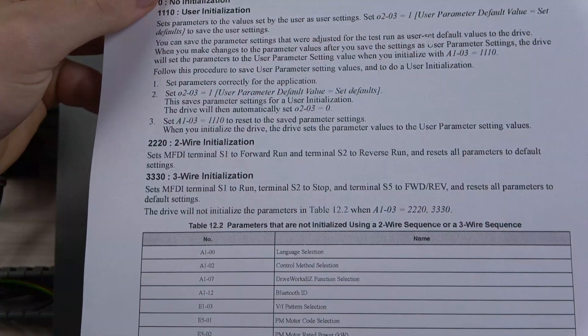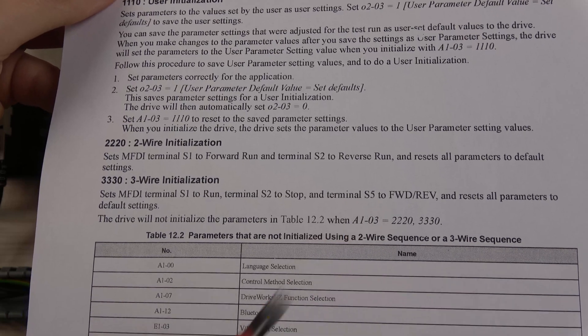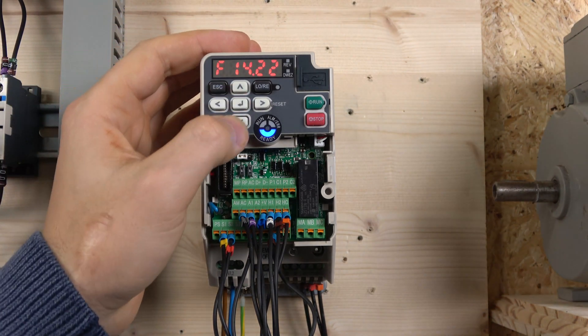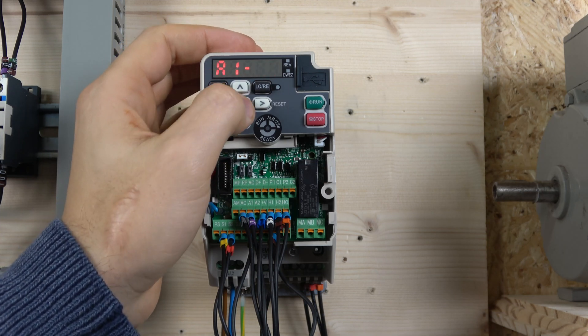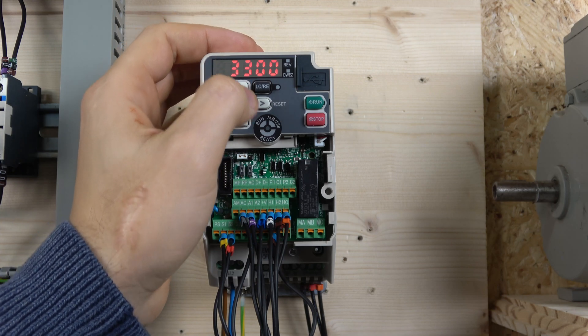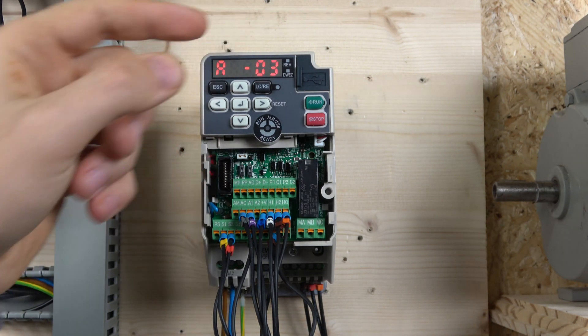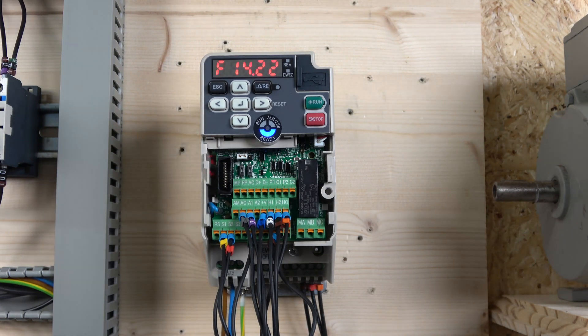In three-wire control mode, S1 becomes the run terminal, S2 becomes the stop terminal, and S5 is used for forward and reverse selection — the remaining S terminals can still be programmed freely. To set this up, go into parameter A1-03, enter the value 3330, and press enter. The drive will rearrange all inputs for three-wire control. Note that every initialization resets all parameters back to factory default, so you'll need to re-enter your motor parameters and re-commission the drive.